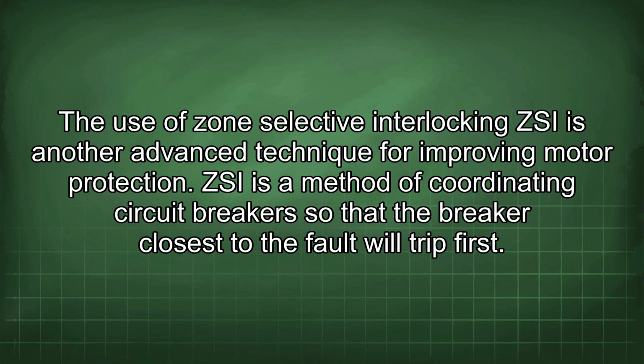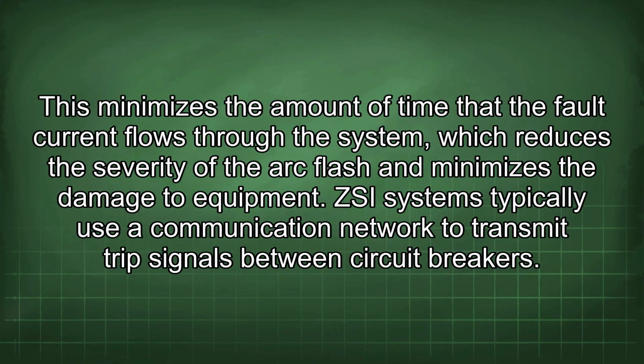The use of zone-selective interlocking (ZSI) is another advanced technique for improving motor protection. ZSI is a method of coordinating circuit breakers so that the breaker closest to the fault will trip first. This minimizes the amount of time that the fault current flows through the system, which reduces the severity of the arc flash and minimizes the damage to equipment.